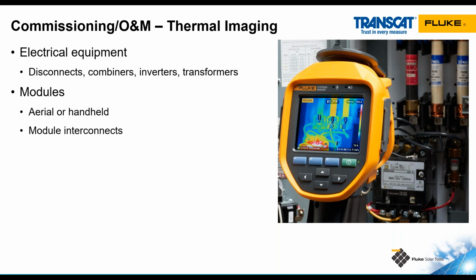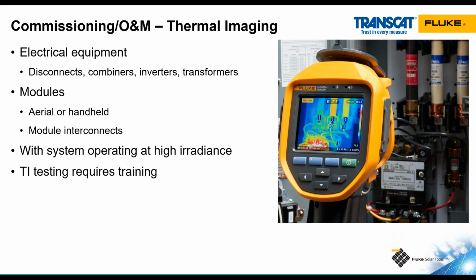We can also use handheld thermography to look at the interconnection between modules to see if we can find high resistance connections there that might be arcing. When we're doing thermal imaging, we need to have the system operating at a high capacity. So we want a higher irradiance so the system is working under load. That's what's going to give us temperature differentials that we can see using thermal imagers. Thermal imaging, unlike many of our other test tools, you can't just take it out of the box and go and take thermal images and expect to get good results.